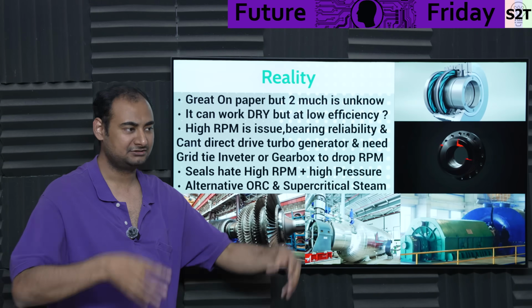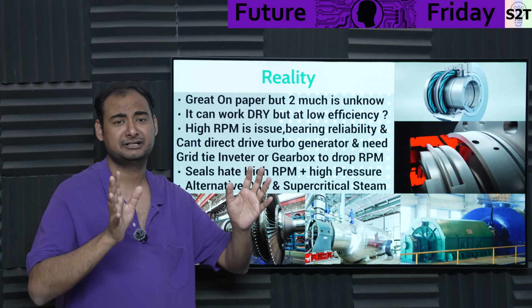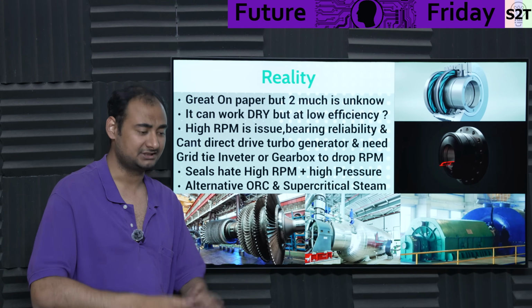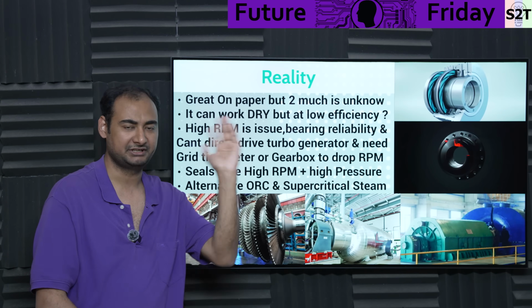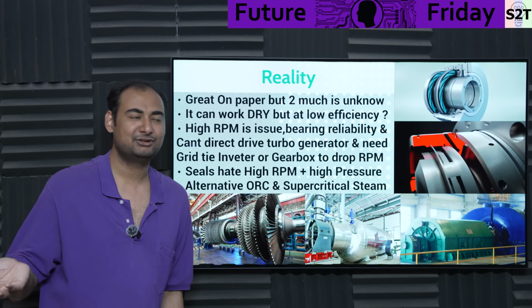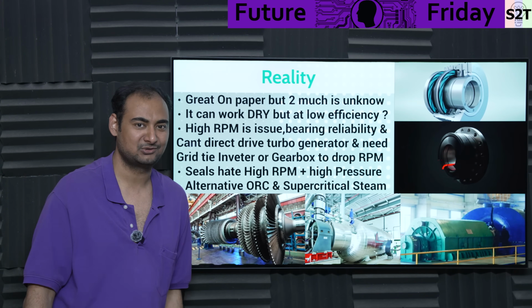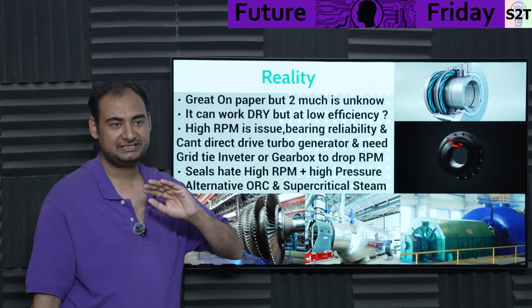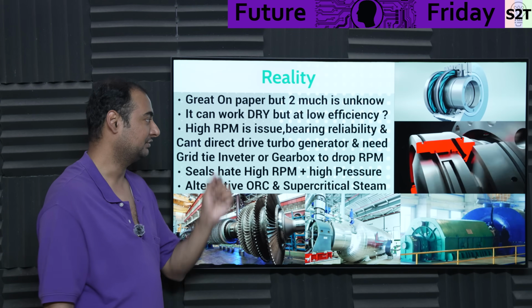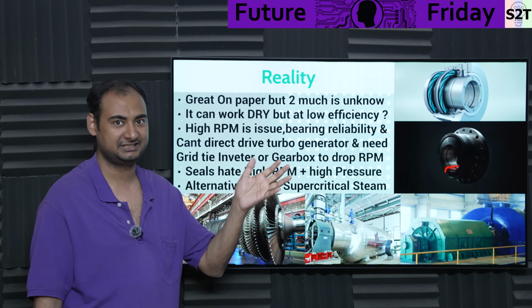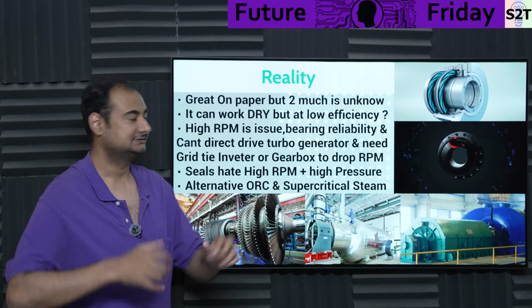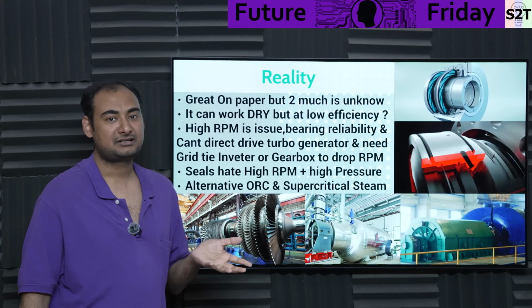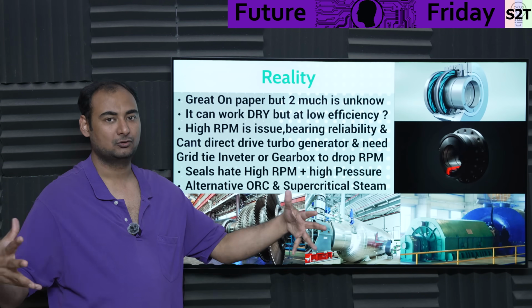Meaning, in a coal power plant, 3000 RPM bearings, they only open it up every 10 years or so when they shut down. That's like, okay, let's check it and validate it or throw it away. Again, if it's running for 10 years, you generally have done your ROI on it. So bearing reliability is inversely proportional to the RPM. So having stupid RPM, 20,000, 30,000, is bad.